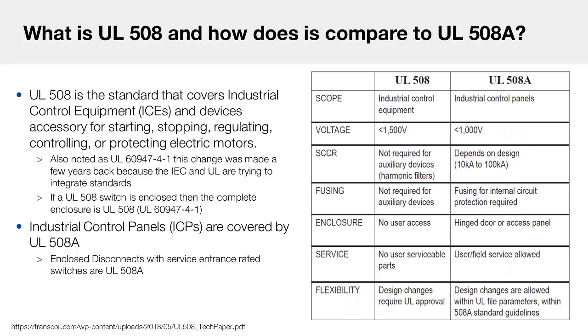A few years back, the IEC and UL standards began to integrate their standards. The UL508 was one of the first standards that has already implemented this integration. So switches that were certified before the integration would list as UL508, which you'll see with some of the Socomec switches, and switches certified after the integration would be certified UL 60947-4-1, which you can see right here on the slide.